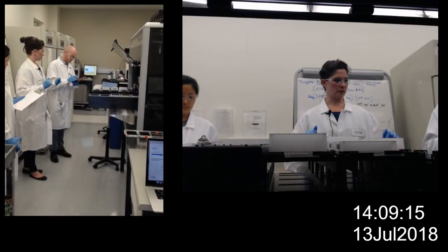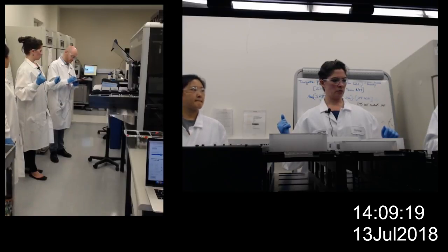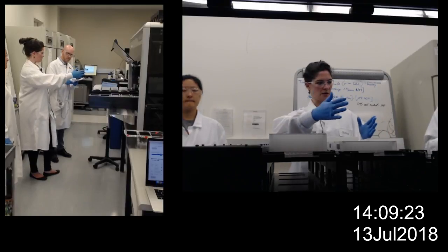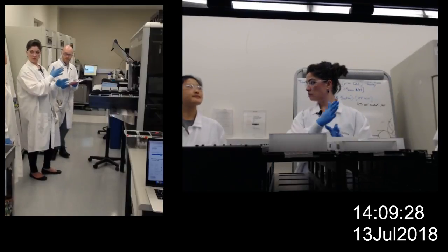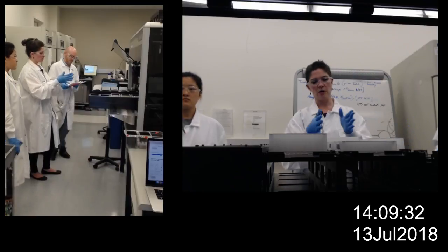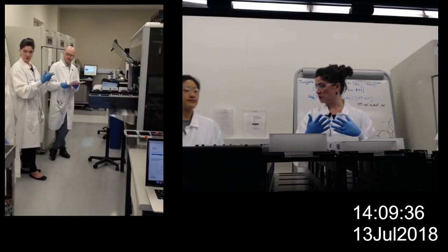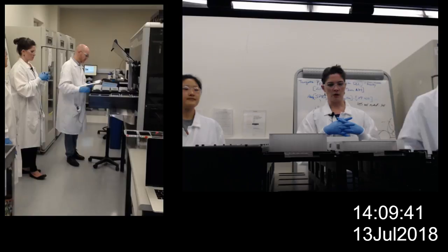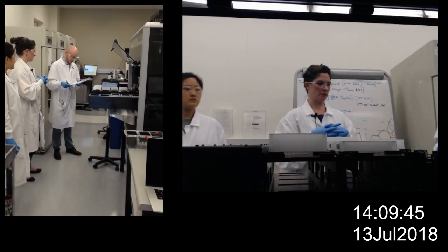So that's a good check. When you're loading, the little happy scanner guy is still scanning as it loads, right? So if I had not noticed that I'd put the tube rack in the wrong place, even though I wouldn't have because it would have stayed there the whole time, it will let you know at that point without aborting anything. So it'll give you a chance to kick back out and fix for those guys at least. Cool. Yeah. Nope, that's fine then.